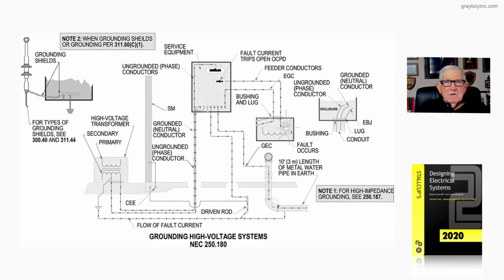Now let's look at this figure 17-22 that deals with grounding high voltage systems in accordance with the requirements of 250.180. Now notice shields is something that we have to ground properly.